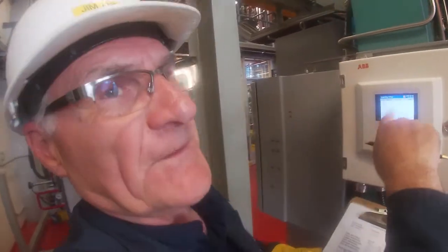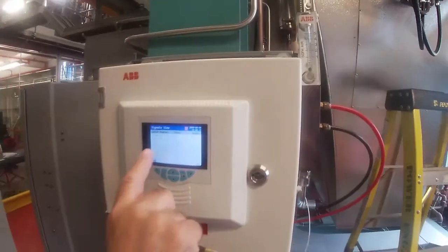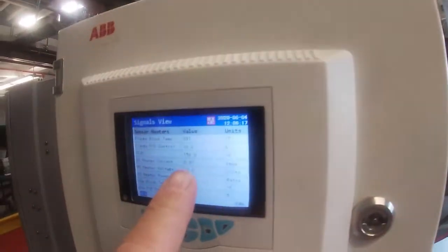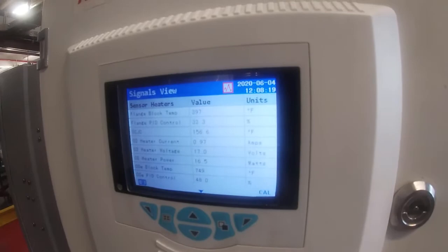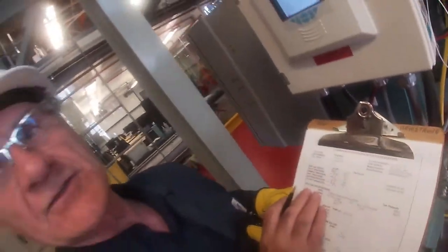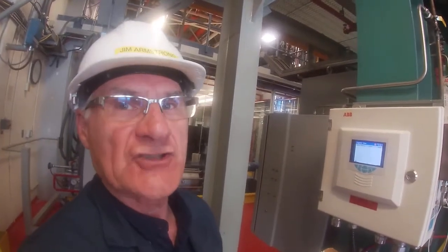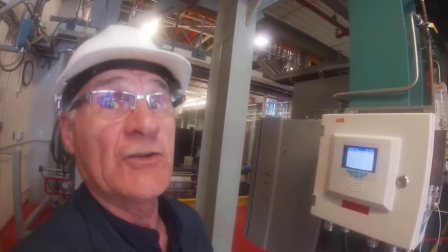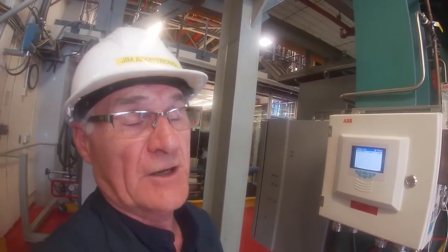From the signals view here, we need to know what the O2 heater current is, and that's at 0.97 amps. What's useful about that is if that current goes up too high or goes down too low, it's indicating that the heater element in there is starting to get in bad shape. It's time to be finding a new O2 cell to replace this one. They're about $600, $650 each, so you're not going to be holding a lot of them in stock. Okay?